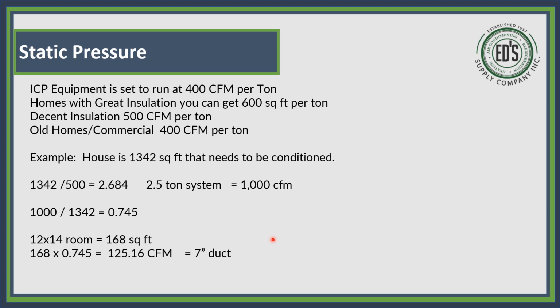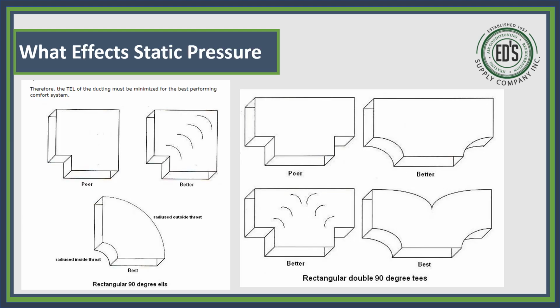Okay, so you've got to keep that in mind. Whatever I'm putting in, I've got to be able to pull back out too. So now we're going to look at our ductwork installs. Square throat, square heel, no turning vanes is very poor. Square throat, square heel with turning vanes is better. But a radius throat and a radius heel is a lot better than even that with turning vanes. That's the best.